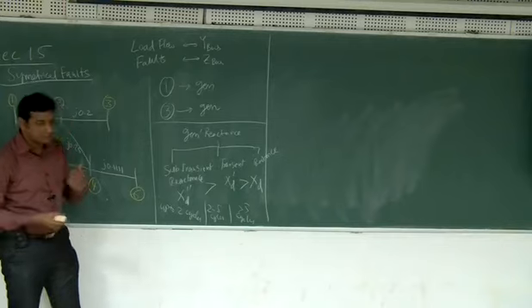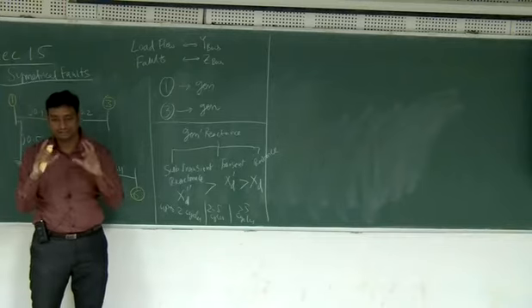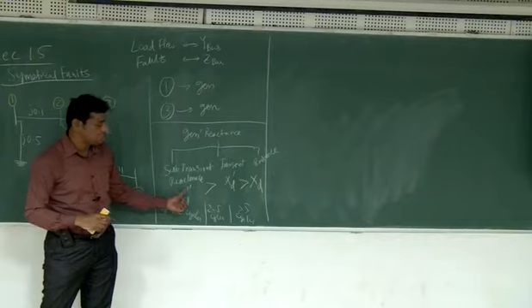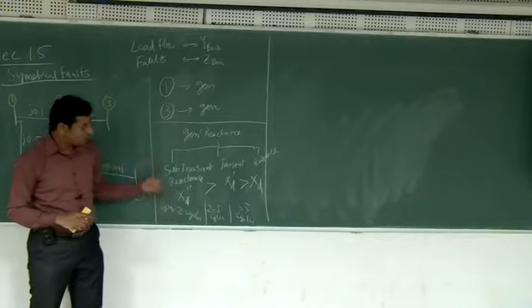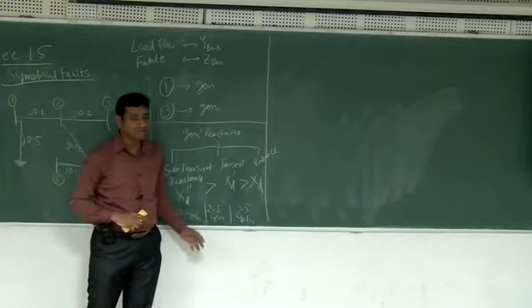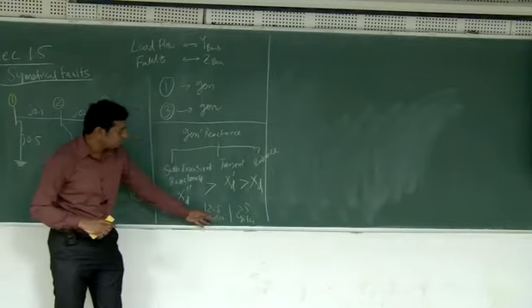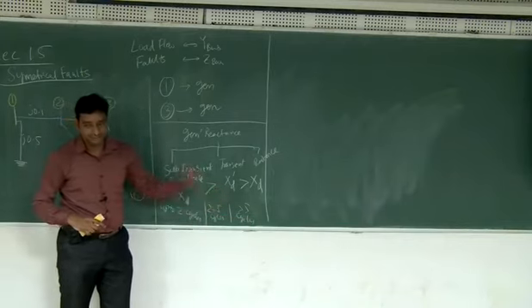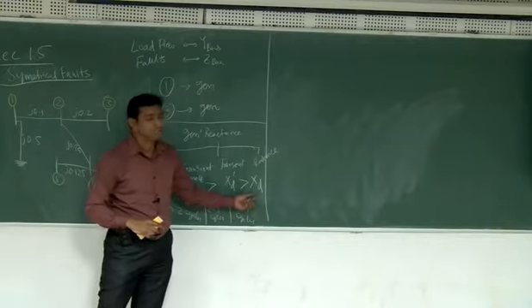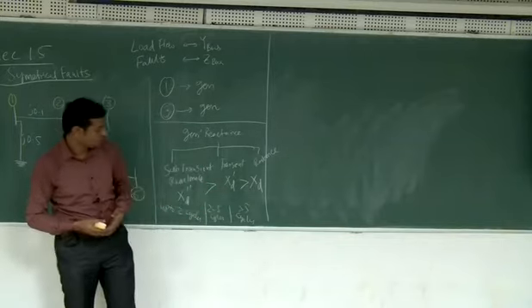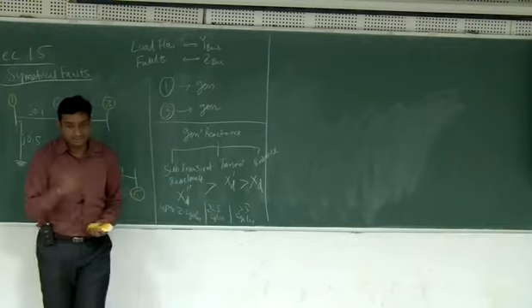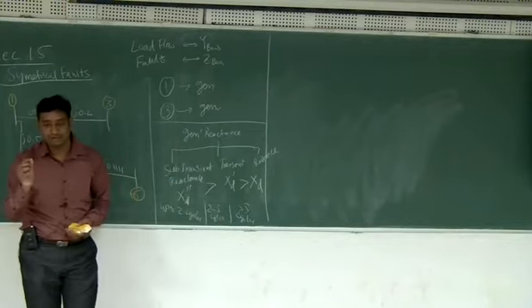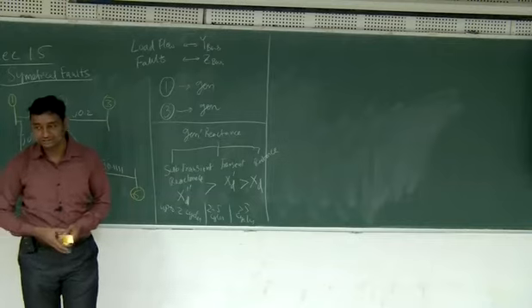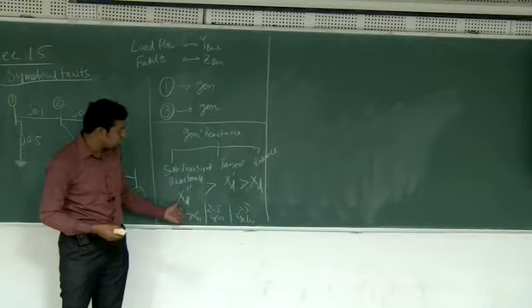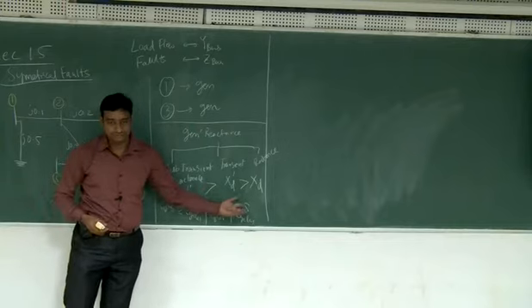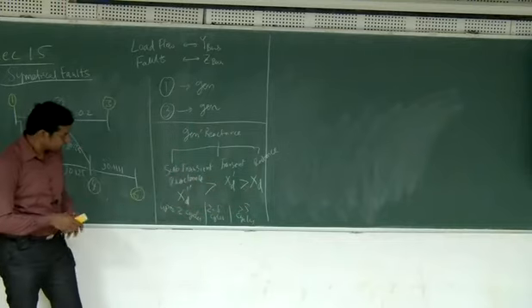For the initial 40 milliseconds, the synchronous machine will exhibit XD double dash as the reactance. Afterwards, between 2 to 5 cycles, this is all approximate numbers, its reactance will slightly reduce. And then later on, this is what we normally use for our regular calculations. Because a fault is a sudden occurrence, immediately after the fault you have to use these values, and then later on, after a few cycles, you have to use the other values.